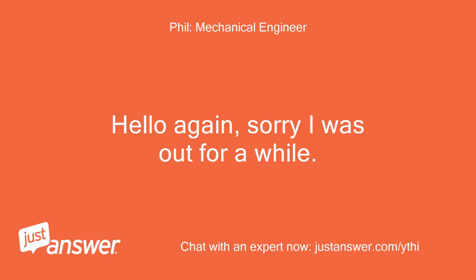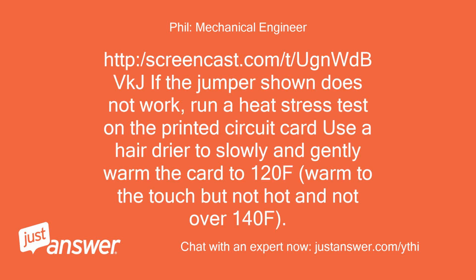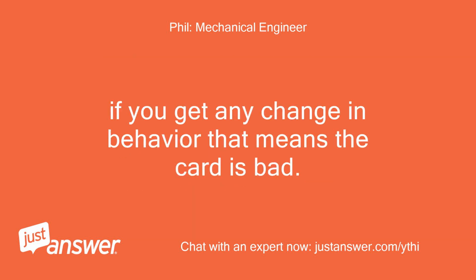Hello again, sorry I was out for a while. If the jumper shown does not work, run a heat stress test on the printed circuit card. Use a hairdryer to slowly and gently warm the card to 120 F, warm to the touch but not hot and not over 140 F. If you get any change in behavior, that means the card is bad.